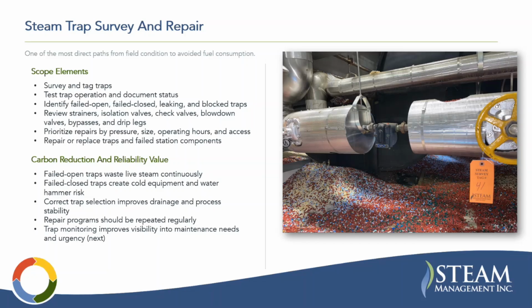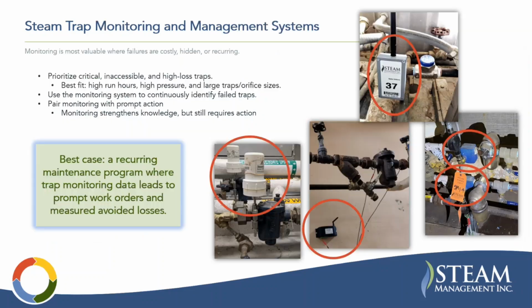So it is just a total waste. It's just blowing steam out of a hole. Generally, when they fail, they can fail closed, which can create cold equipment and water hammer risk. That's usually from some sort of plugging of the hole of the trap or the orifice. Correct trap selection improves drainage and process stability. A repair program should be repeated regularly, and trap monitoring improves visibility into maintenance needs and urgency, which we'll talk about on the next slide.